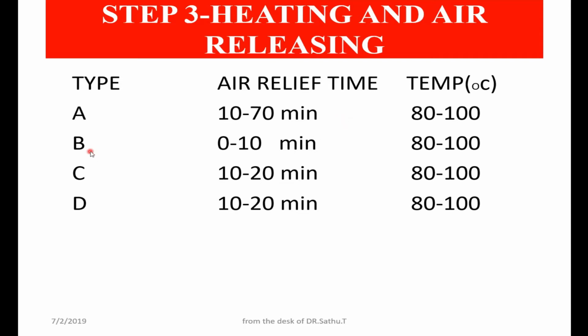In the product B, that is blood, it takes around 10 minutes. If it is feather, it takes around 10 to 20 minutes. And if it is mixed poultry offals, it will take around 10 to 20 minutes. And the temperature, we can see, comes around 80 to 100 degrees centigrade.